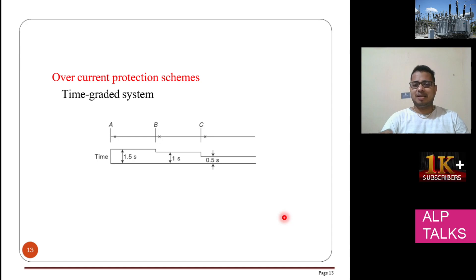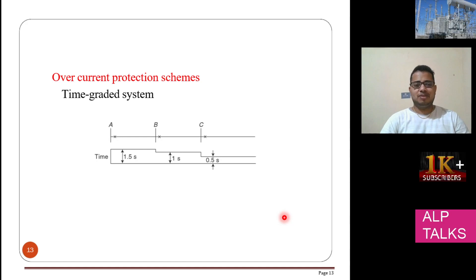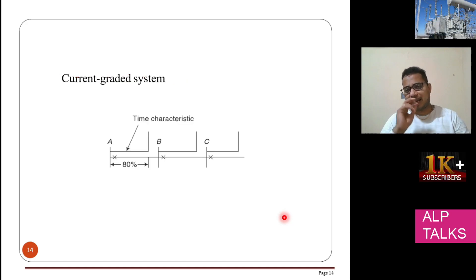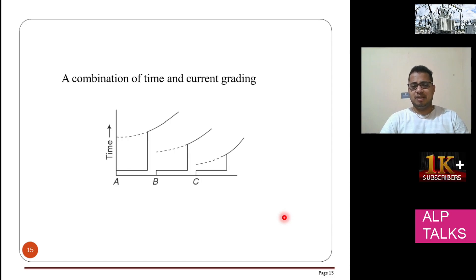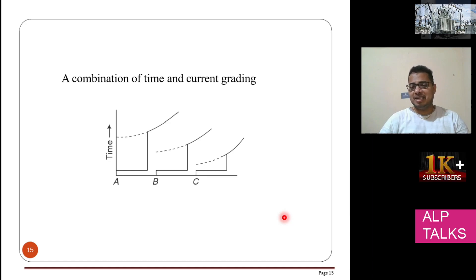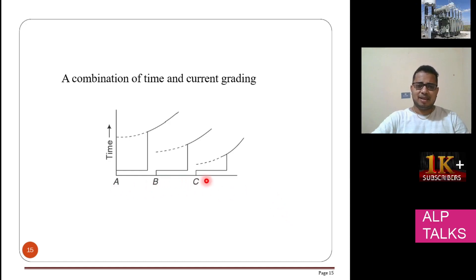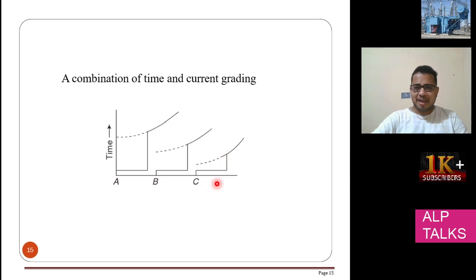This is one of the better techniques. You also have current grading: if 80% of the current threshold is reached, A operates; if it exceeds further, B operates; and if even higher, C operates. There is also a combination of time and current grading. A operates for low current, B for high current, and C for very high current. If the current is very high, the relay needs to operate very quickly — that is what the graph shows.